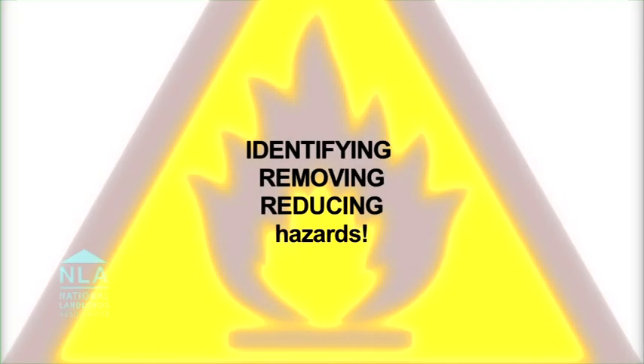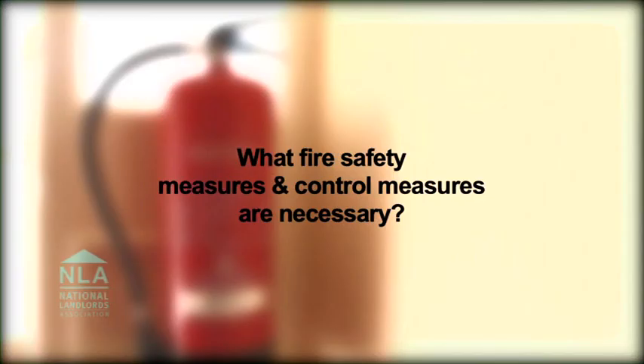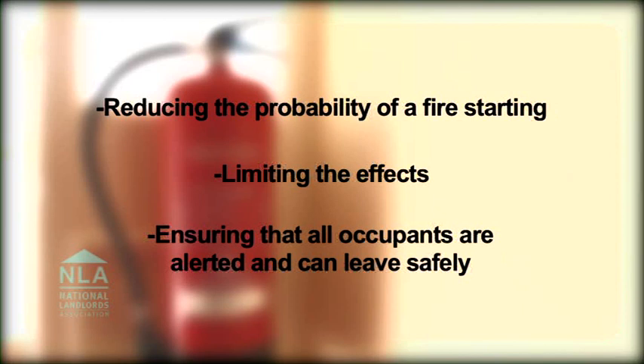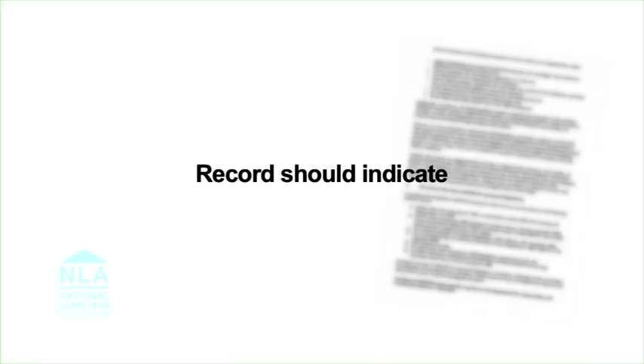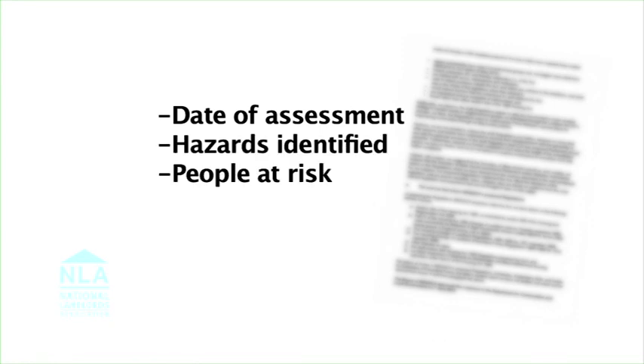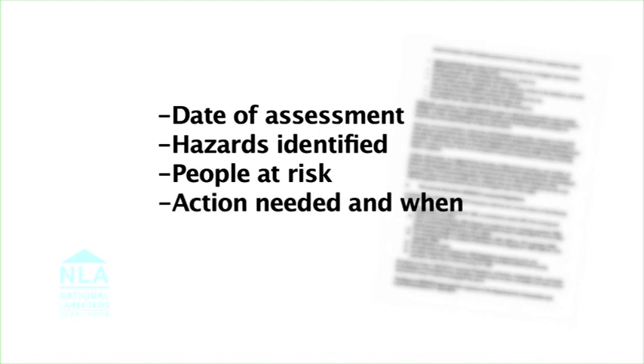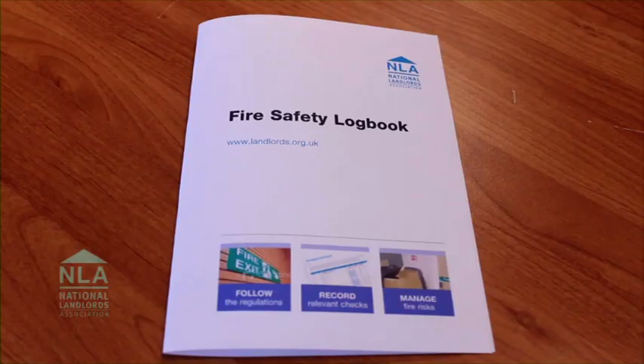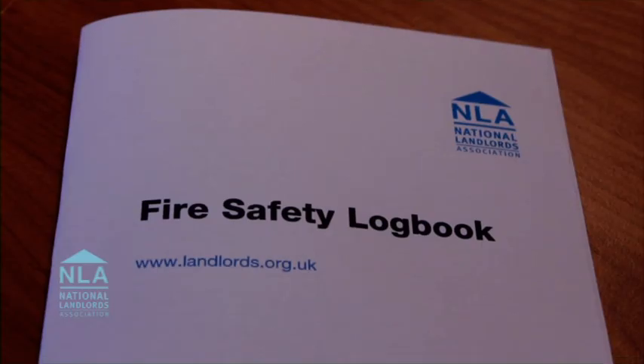This will encompass identifying fire hazards and people at risk. You will need to determine what fire safety measures and control measures are necessary to ensure the safety of people in the building should a fire occur, by reducing the probability of a fire starting, limiting the effects should a fire occur, and ensuring that all occupants are alerted and can leave the premises safely in the event of a fire. The record should indicate the date the assessment was made, the hazards identified, any people especially at risk, what action has been and still needs to be taken and by when, and the conclusions arising from the assessment.